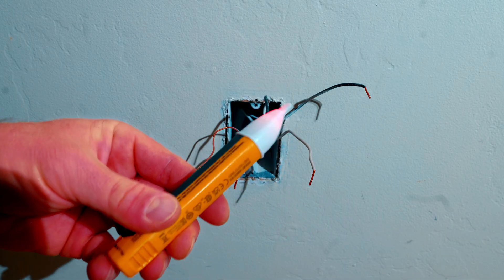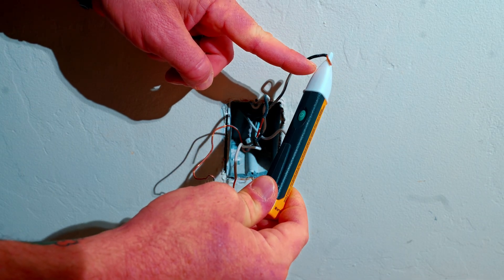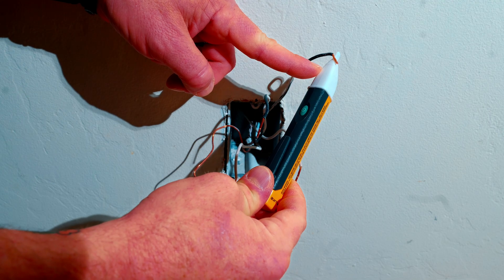I've made it back from shutting power off. We're just going to double check that power is actually removed — you can see it is not flashing on our line hot wire, so we do know the power is back off and it's safe to work on the circuit.